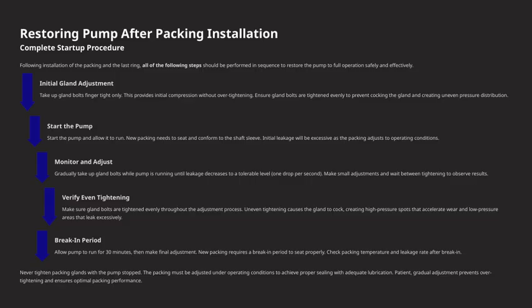Once you've completed the packing installation, it's essential to follow a complete startup procedure to ensure safe and effective operation. First, start with the initial gland adjustment. Take up the gland bolts finger tight only. This gives us initial compression without over-tightening, which is crucial. Then, make sure to tighten the gland bolts evenly. Uneven tightening can cause the gland to cock, leading to uneven pressure distribution and potential leaks.